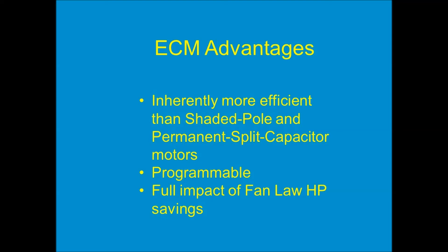Finally, these EC motors that we supply with our fans give you the full impact of the fan law horsepower savings. Remember, with the fan laws, when you reduce the flow you get an exponential savings on the electric bill because the horsepower requirement drops so drastically. You get that full effect with the EC motor. With older technology — direct drive fans using a permanent split capacitor motor on a speed control switch — you didn't get any energy savings because a lot of the voltage was just being converted into heat in that switch. Yes, it was slowing down the fan so you could balance the airflow, but you weren't saving any energy. Now with the ECM, you actually get the full effect of the fan laws.